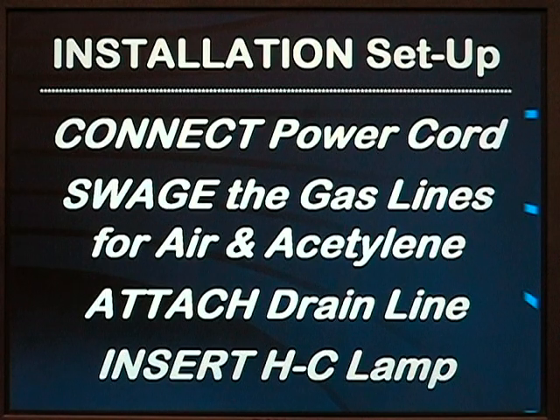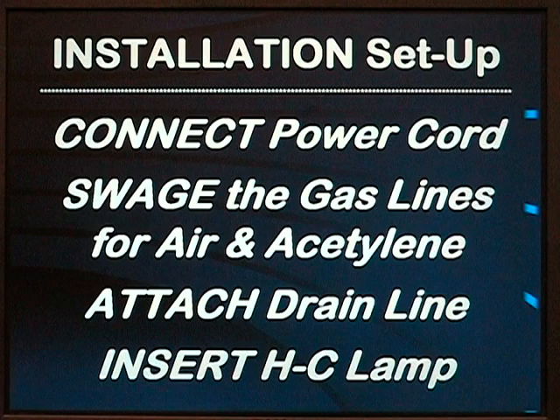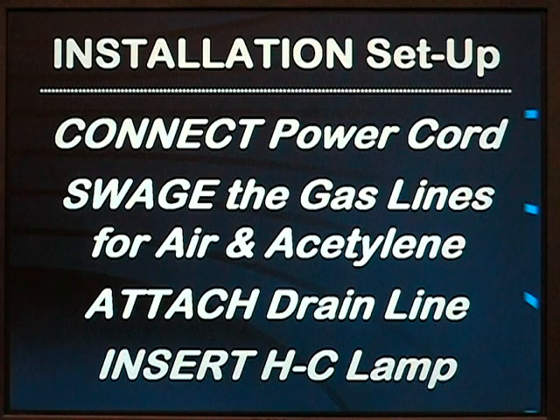To continue with the installation setup, you will have to connect the electrical power cord for the instrument, create a gas-tight Swagelok fitting for the gas lines for the air and acetylene and nitrous oxide if used, attach the Tygon drain line with a loop to prevent flashbacks, and insert the hollow cathode lamp for the element you are going to use for your first analysis.